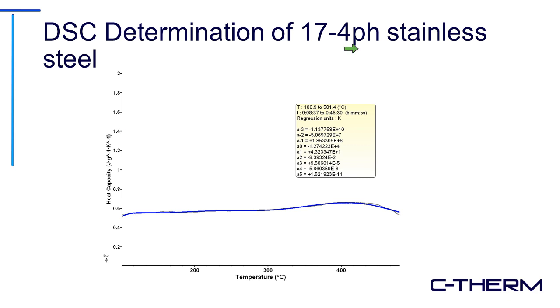So this is exactly what I did in this run. We looked at stainless steel AM powder, and specifically from 0 to around 500 degrees Celsius. You can see that the heat capacity does change with respect to temperature, which is important to know as you're over time. But so by measuring this, we're able to show that specifically at different temperatures, the heat capacity of that powder with respect to the process that you're trying to generate. So if this is in a stream, you want to know specifically the stream is running at 200 degrees Celsius, we're able to calculate that heat capacity, which is very important when you're doing modeling of these processes in general.